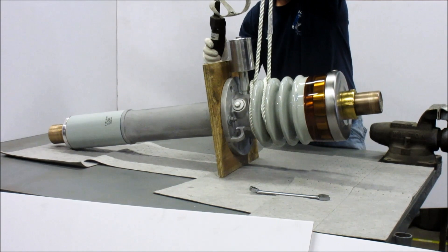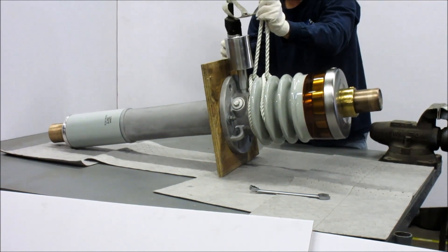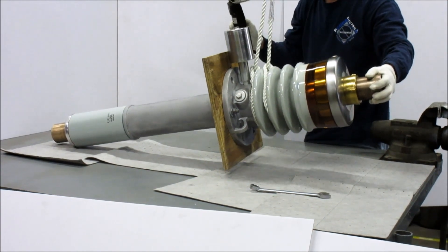Install the bushing into the equipment or wall while keeping the oil expansion reservoir above the bushing and keeping the bushing horizontal.